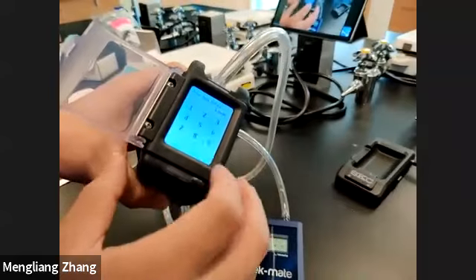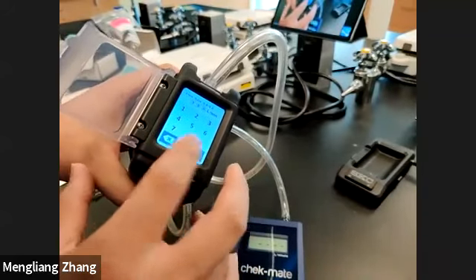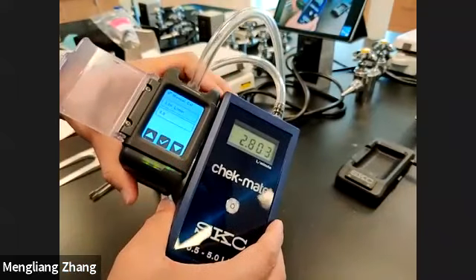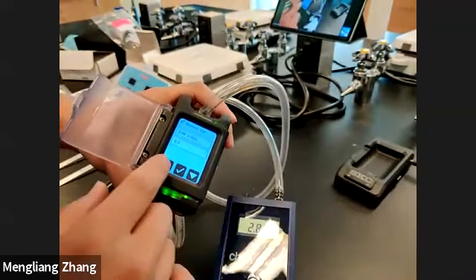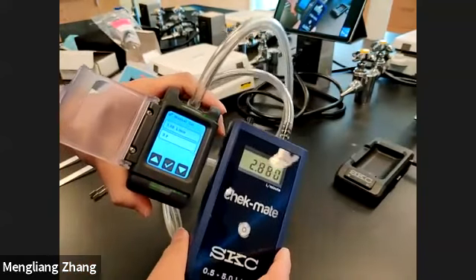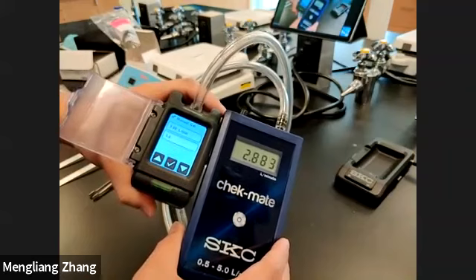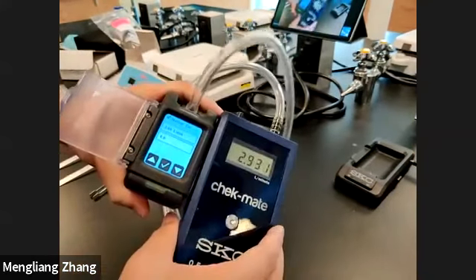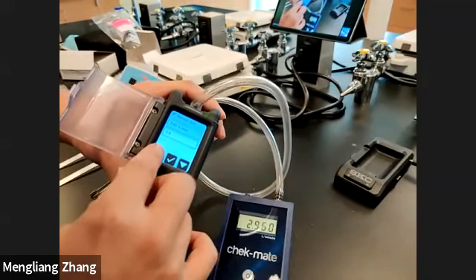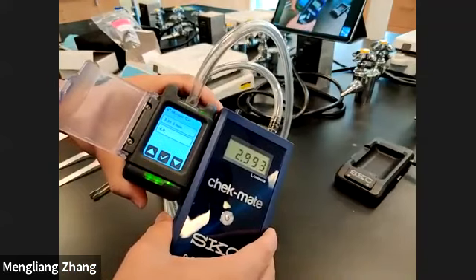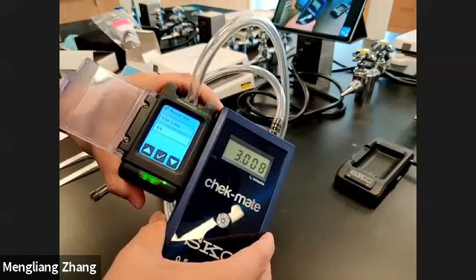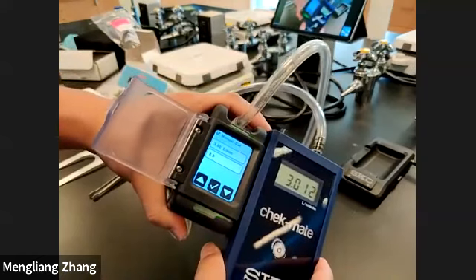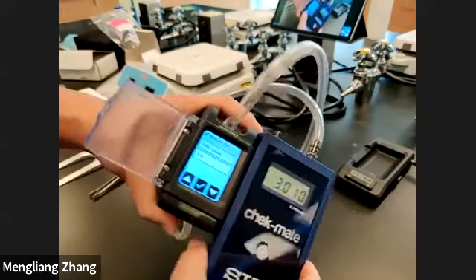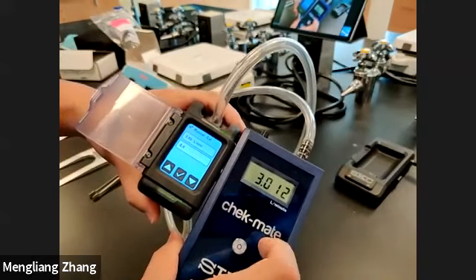We still select the manual calibration, and yes, we input 3.00 liters per minute. The real-time airflow is 2.8, so I can increase this adjustment factor. Then I can see an increase of airflow from the calibrator. By the way, I need to increase more. Okay, it's not there yet. Let's just increase to 8. After I increase this adjustment factor in the second row, just by pressing this arrow button, now the airflow is very close to 3.00 liters per minute.